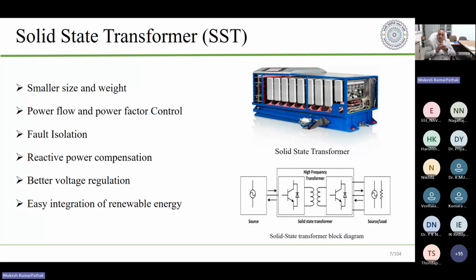And in fact, by increasing the frequency further and further, a transformer of 1000 kg can become a transformer of some 100 kg. And transporting a 100 kg unit as compared to a 1000 kg transformer is an entirely different matter, because handling a single unit of 1000 kilograms is much harder than handling a 100 kilogram unit. As I said earlier, the conventional transformer has no power flow control and no power factor control. This transformer, because of its inherent power electronics, will offer power flow control and power factor control also.